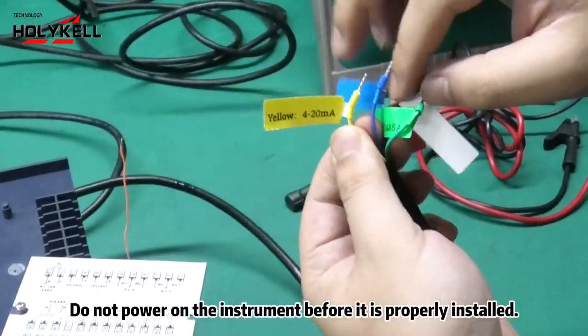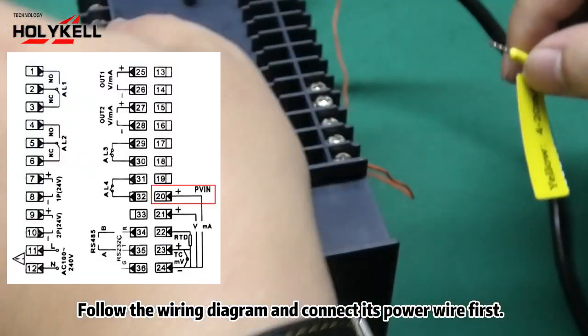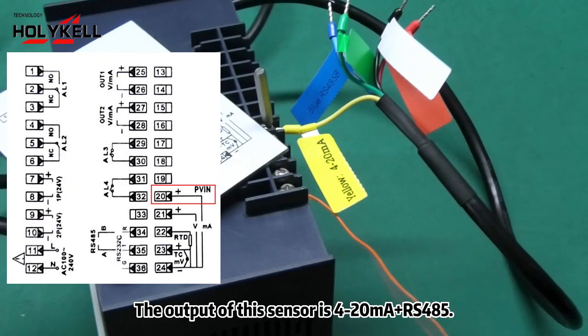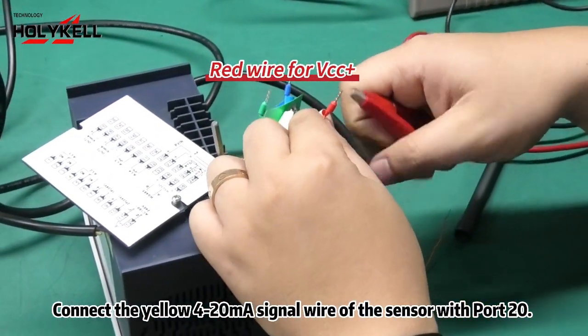Do not power on the instrument before it is properly installed. Follow the wiring diagram and connect its power wire first. The output of this sensor is 4-20mA RS-485. Connect the yellow 4-20mA signal wire of the sensor with port 20.